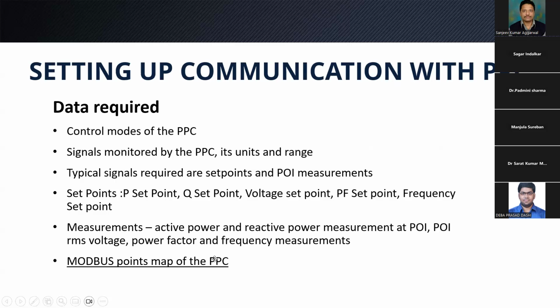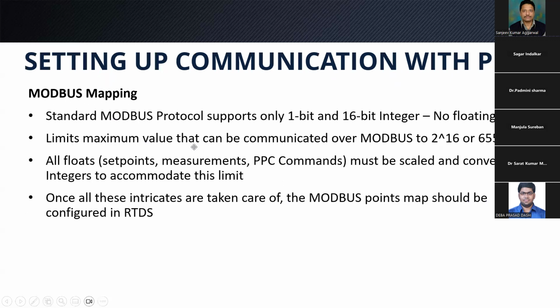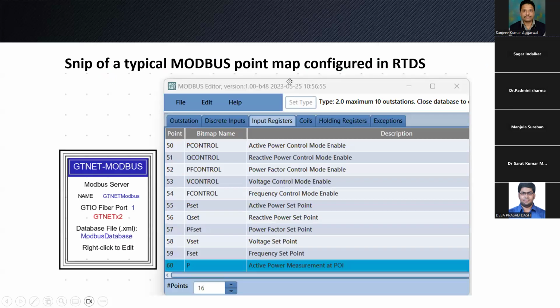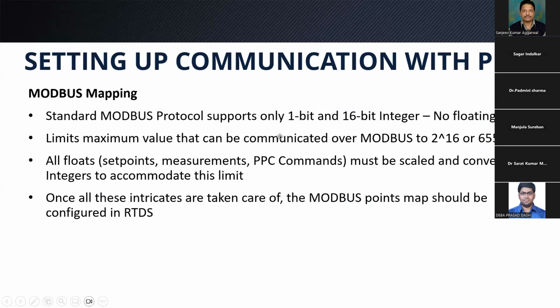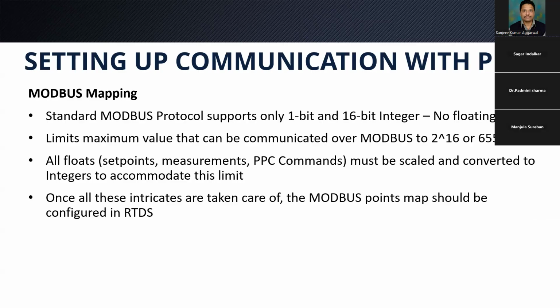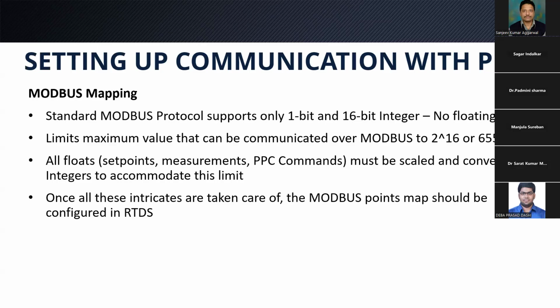What is Modbus mapping? For the PPC, we do that using what we call a Modbus editor. We specify all the set points, measurements, and commands, and these can be done through one of the four methods. Modbus supports 16-bit integers only, so it cannot support real numbers. So we have to do some scaling conversion so that decimals can be accommodated. Typically we scale it so that all decimals become integers, and then internally in the controller we can scale it down to the desired level.